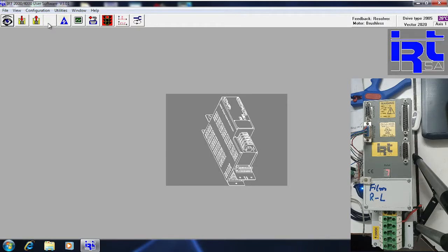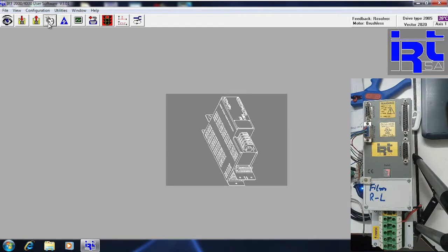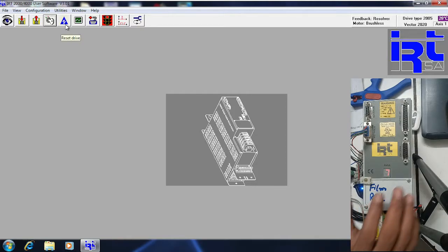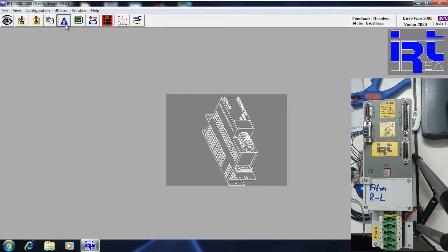I must save it to the drive flash memory. As I click the flash button, you will see it blink for about half a second, which indicates the parameter has been saved to flash. This is the reset drive icon — when I press it, you will see it change from 0 to 7, which means the drive has been reset. This is the scope and monitor window, which we will not cover today.